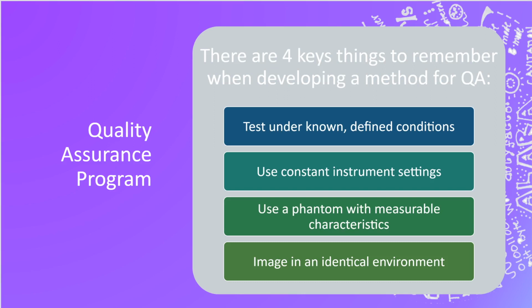Using a phantom with measurable characteristics is going to help us to identify what we should be able to see. The phantom tells you exactly what should be seen, and then we can use the machine settings to make sure that nothing changes from time to time as we are trying to view those objects in the phantom. Again, we'll talk a little bit about this more in a second here.